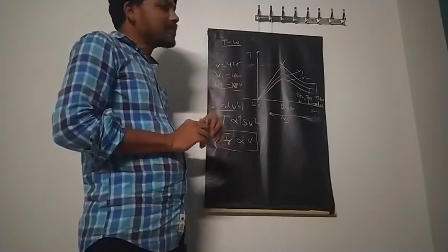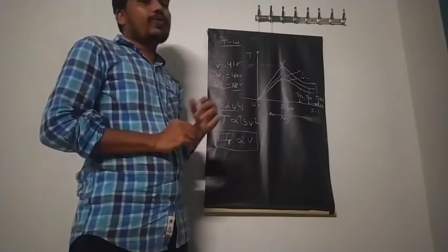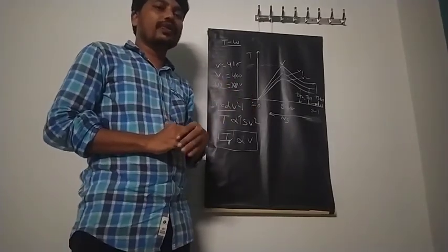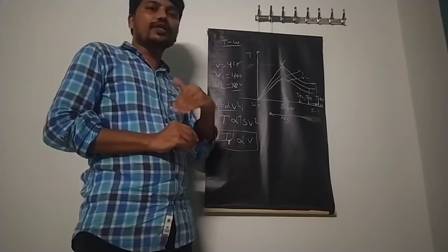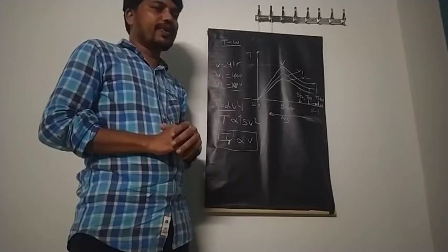So what are the limitations of this stator voltage control method? It is not suitable for speeds beyond the rated value, because going beyond the rated voltage is not possible. Therefore, speed cannot be more than the rated speed. That is the main limitation.